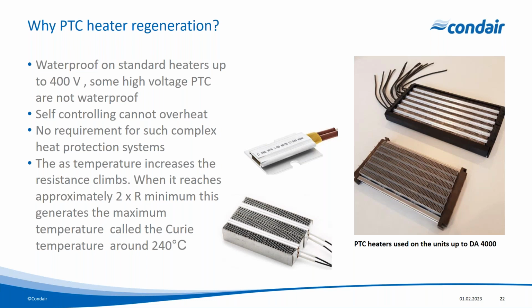But basically, as the temperature increases, the resistance in the heater climbs. When it reaches approximately 2 times R minimum, this generates the maximum temperature called the Curie point, or the Curie temperature, which is around 240 degrees C. We don't actually reach there, but because it's self-limiting, because the resistance climbs, its potential to generate heat reduces. So it's self-limiting. And it being waterproof, it's incredibly safe.